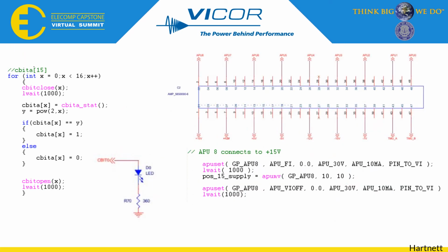For the C bits, these are the relays being verified. There are 64 C bits divided into 4 banks, banks A through D. The code shown is a test designed to verify the first 16 C bits, bank A. The tester reads the C bit values in 2's complement, so with 64 C bits to verify, we found it easier to convert all the values so that when the C bit is supposed to be on it displays a 1, and displays a 0 when it is off.